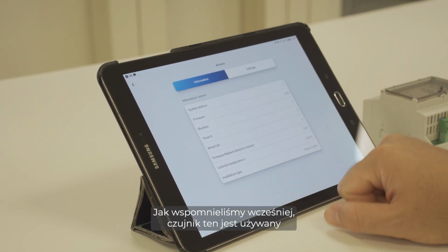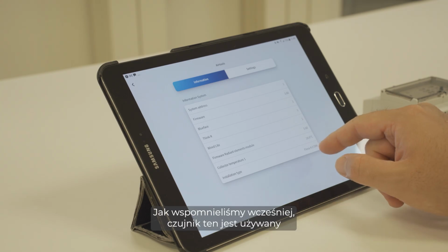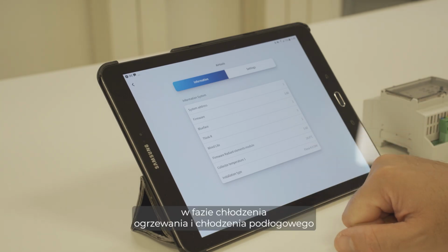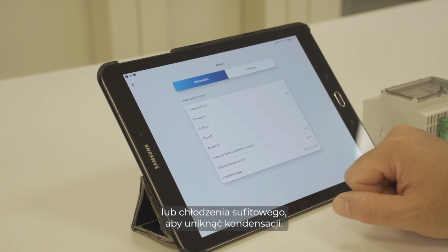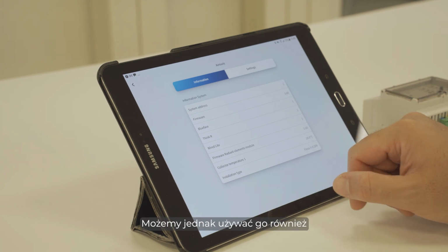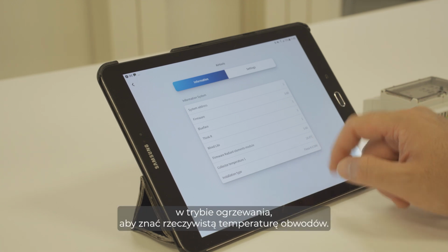This probe, as mentioned before, is used in the cooling phase of underfloor heating, underfloor cooling, or ceiling cooling to avoid condensation, but we can also use it in heating mode to know the actual temperature of the circuits.